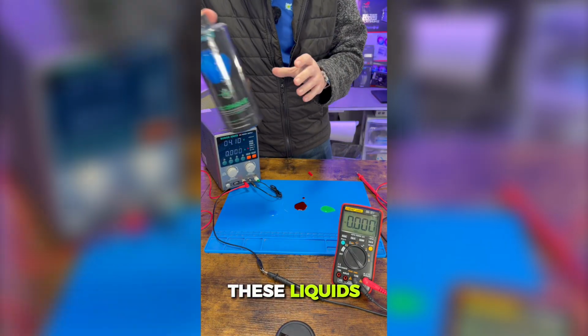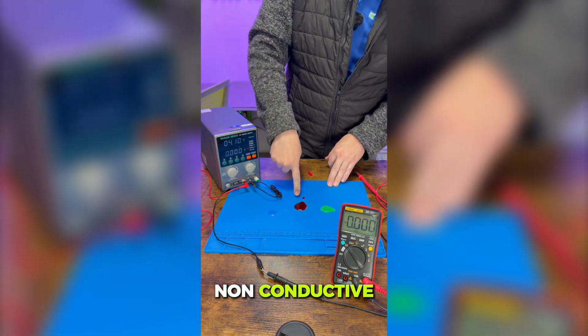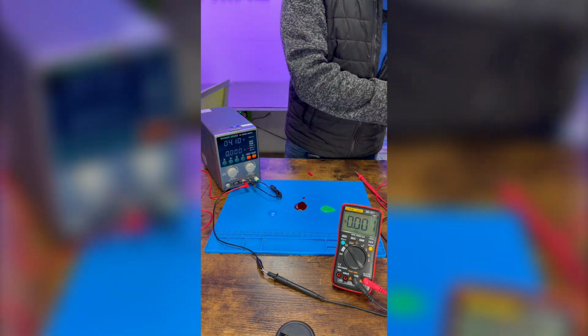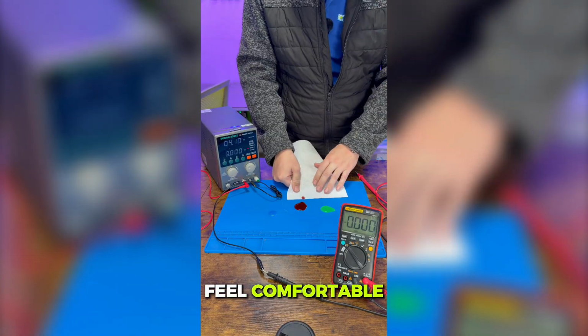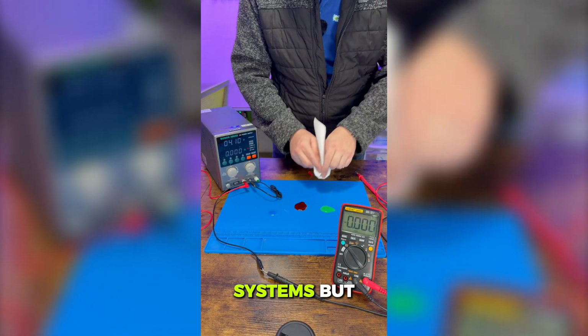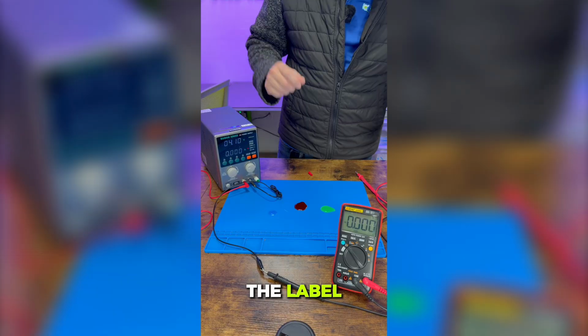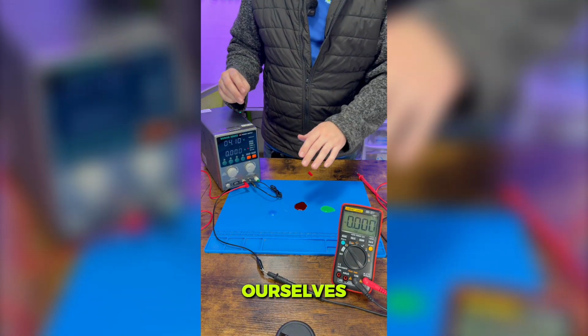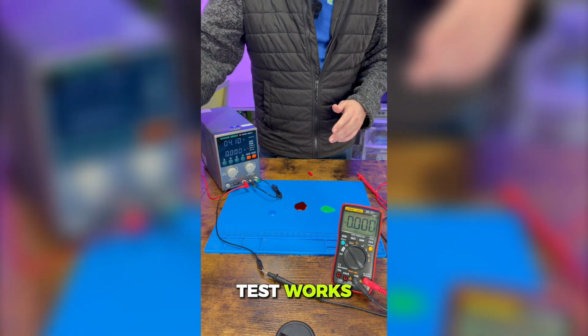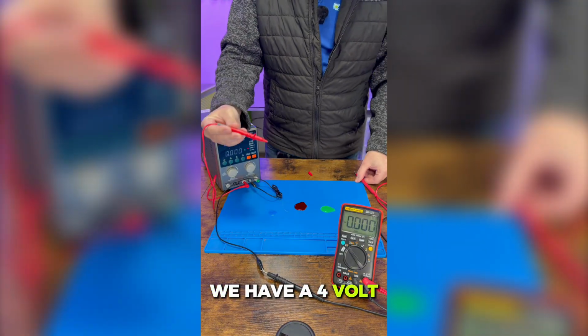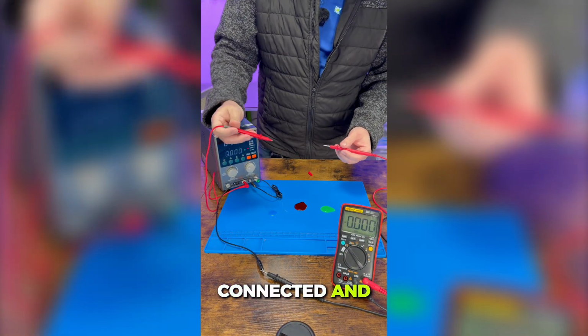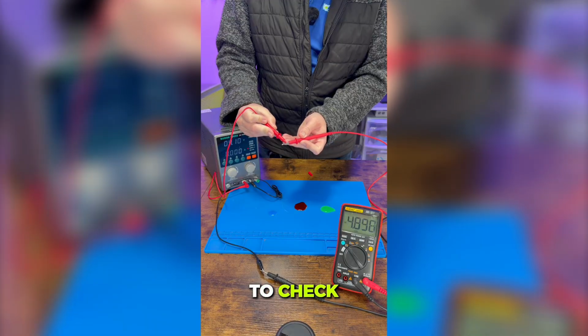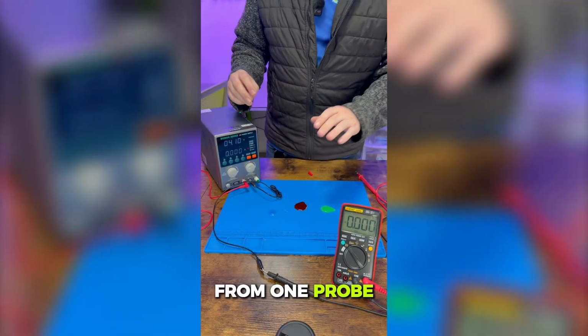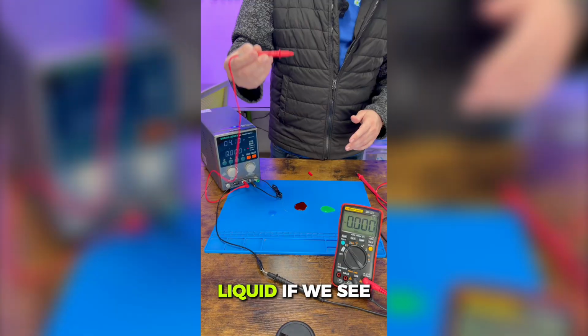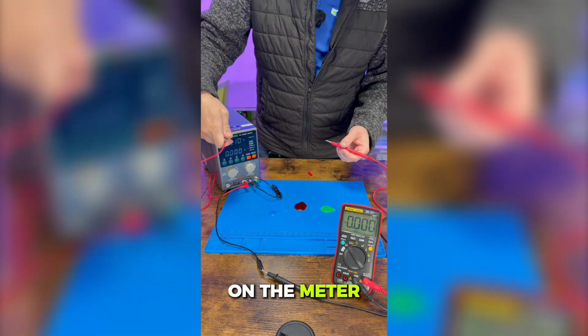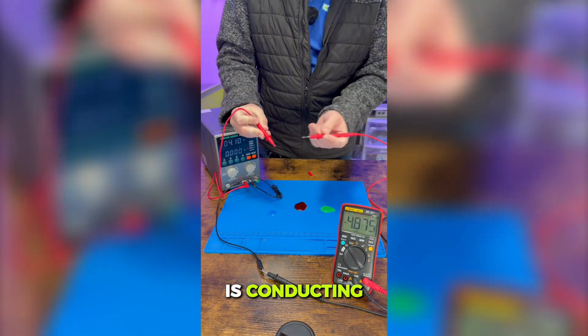These liquids are marketed as non-conductive or low conductivity, which is why many people feel comfortable using them inside their systems. But instead of trusting the label, we're going to measure it ourselves. Here's how the test works: we have a 4-volt power source connected, and we're using a multimeter to check whether current can pass from one probe to the other through the liquid. If we see voltage on the meter, that means the liquid is conducting electricity.